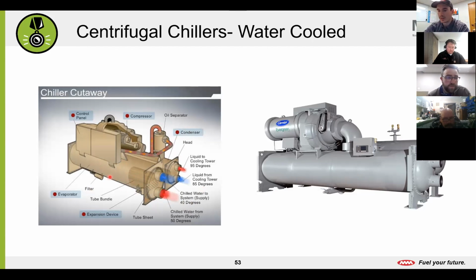Well, when we absorb heat from that water, we have to reject it somewhere. So it puts it into the condenser barrel where we're able to reject that heat into the condenser water loop, which we were kind of talking about earlier. And then that goes up to a cooling tower, which I'll show you here. We'll go through that and we reject that heat outside. So these are typically a lot bigger. They're able to be installed inside.